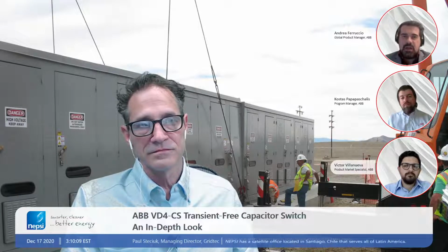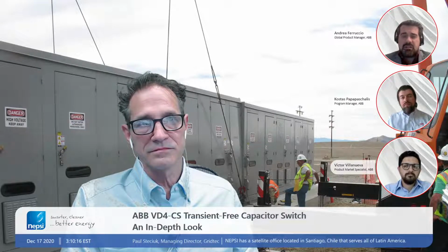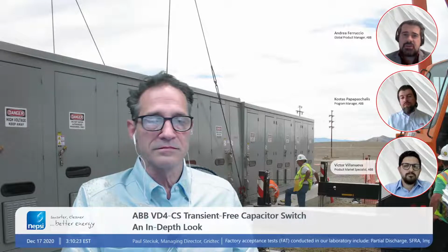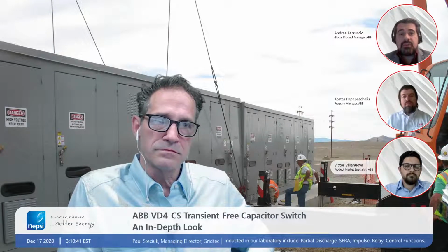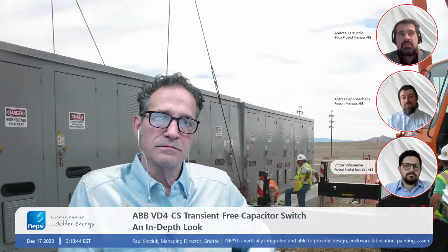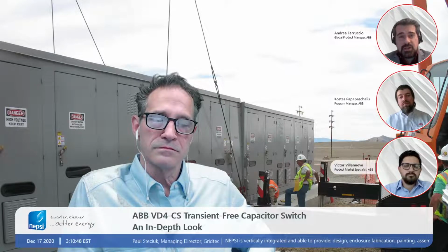We are talking about mentioning VD4-CS and DS1, two products that are basically for different applications, for two different voltage levels and also types of installation. The VD4-CS is a complete circuit breaker, offering the possibility of transient-free switching and the protection against short circuits. The DS1 instead is a pure switch. The difference also is the fact that we are using the VD4-CS for all those applications with ungrounded Y capacitor banks with voltage level up to 38 kV. The DS1 can reach typically 15 or 17 kV voltage levels.